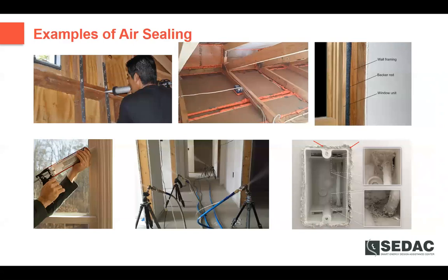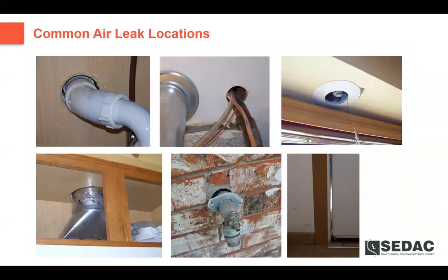I think DOE funded some of this research too, and it's quite interesting. I've done a lot of blower door testing with some colleagues in the past, and these are just some of the common air leak locations beneath vanities and kitchen sinks.